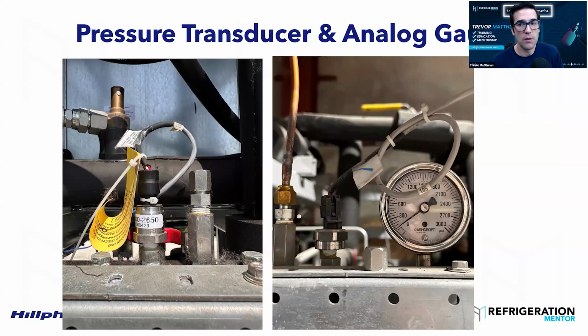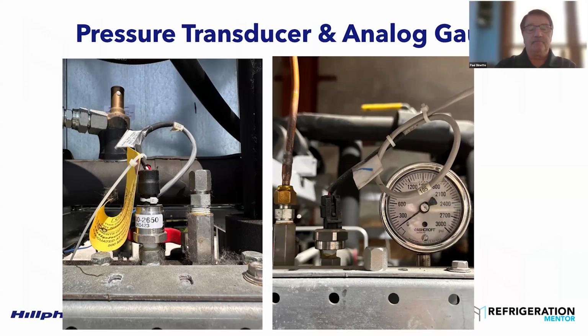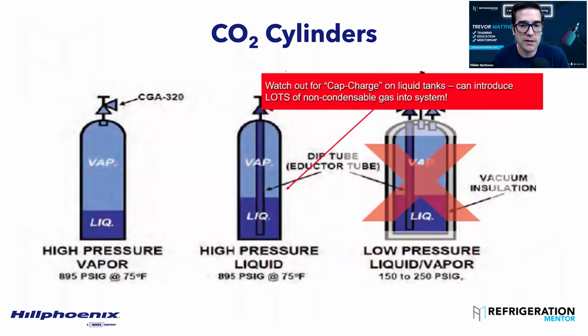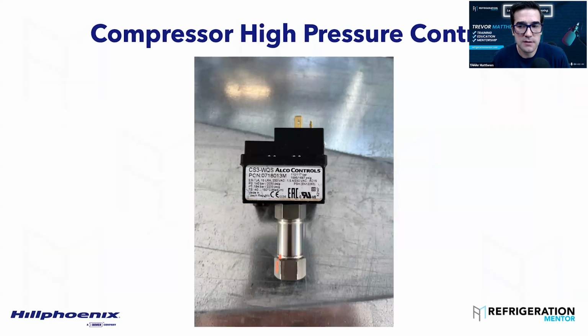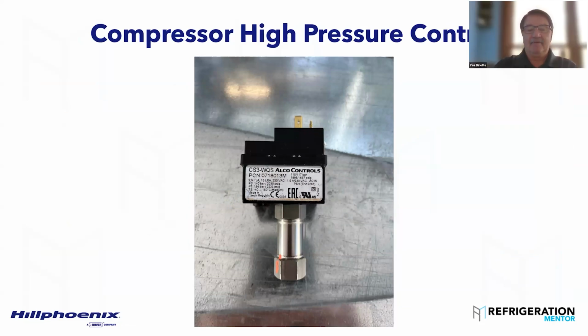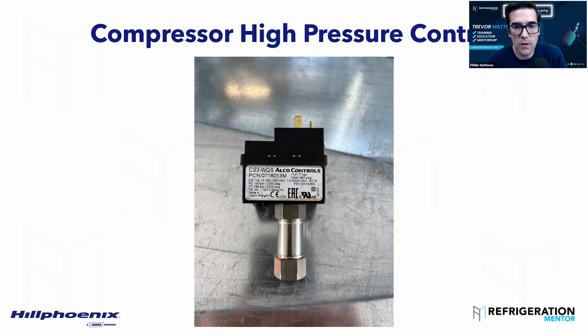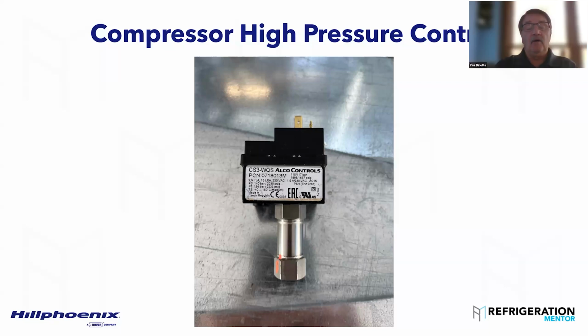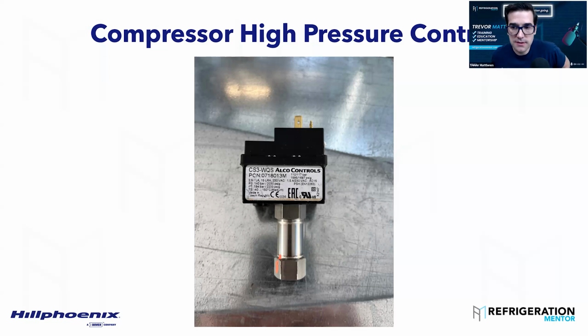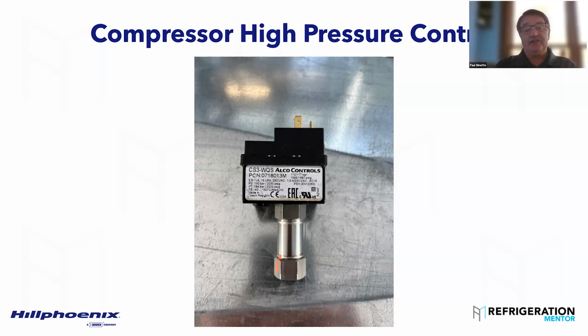So you pull off the wiring, the supply that goes to the switch. We've got an image of that in a little bit. Let me just go to it right quick, because that was a good question that was asked right here. Right, this is the one you're talking about. Yep, that one right there. So you pull 110 bar, 117 bar, like almost 1600 psi to 1700 psi. So you'd take the screw off and you would unplug the wire from this device, right? Yes, sir. Then you're going to look at your proof, and your proof should go from on to off. And then all of a sudden, I can tell you, testing it with a wrench, the CO2 pressure builds up fast enough that it can go right past that switch and hit the relief valve.